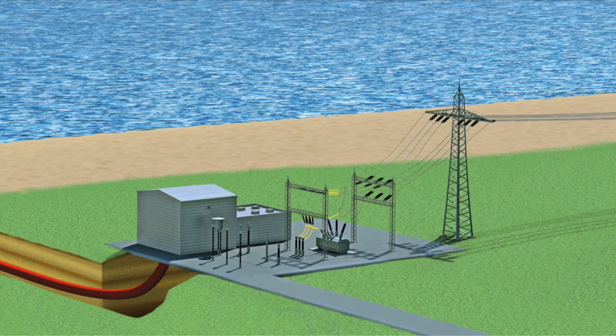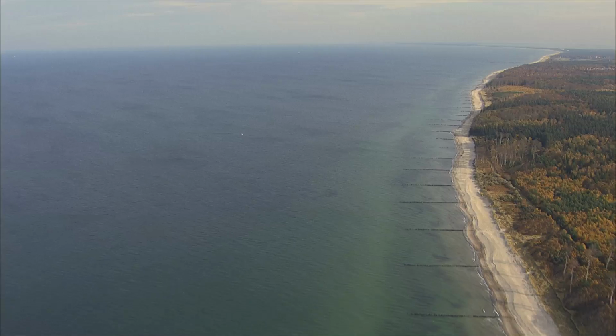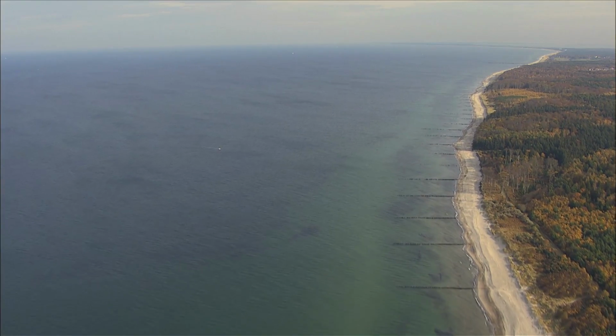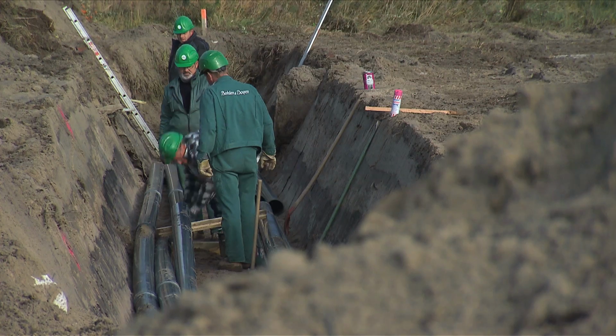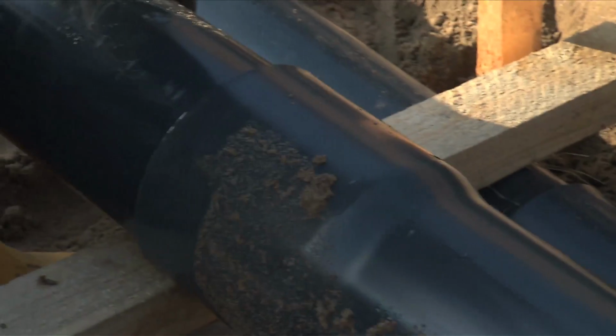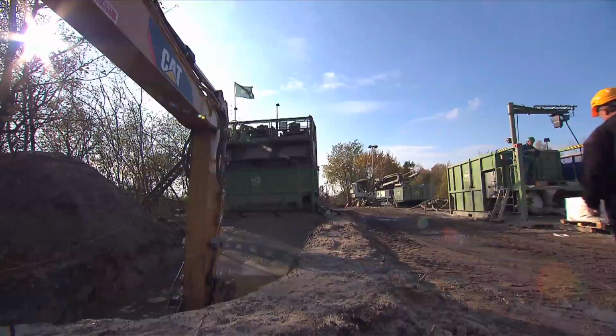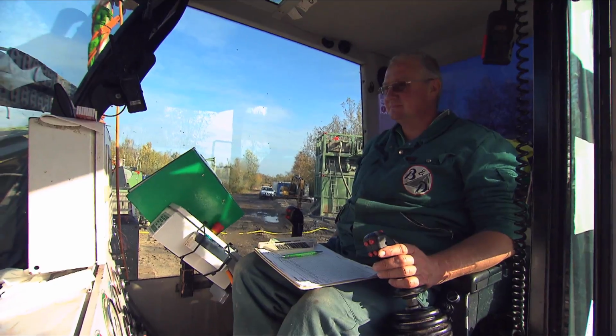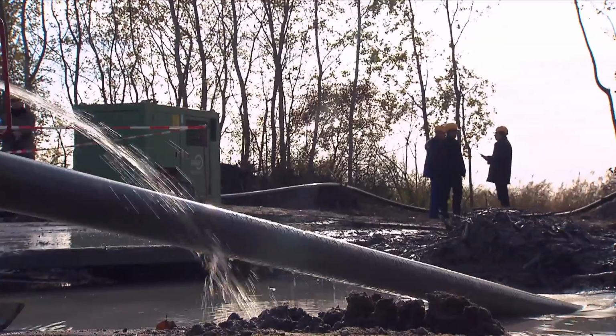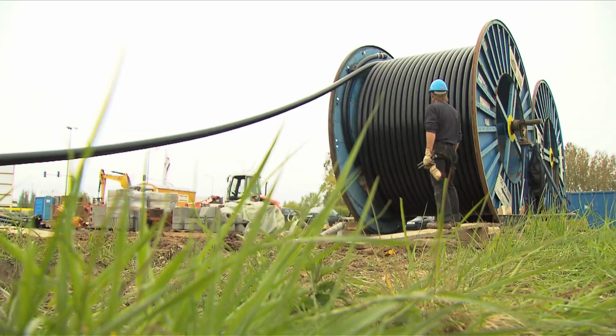This is new territory for all participants. For the connection to the grid, 61 kilometers of extra high voltage cables have to be laid into the ground of the Baltic Sea. 16 kilometers have to be installed on shore, where the cable is laid in 1.5 meter deep ditches protected by pipes.